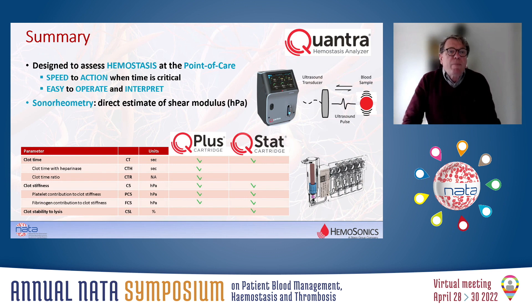In summary, the Quantra hemostasis system is designed for ease of use at the point of care. Sonorheometry is a unique system based on ultrasound measurement that allows a direct estimate of the shear modulus. By using the two cartridges, you get a total assessment of hemostasis in terms of clot time, clot stiffness, and clot stability to lysis.